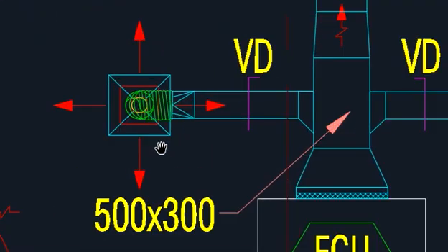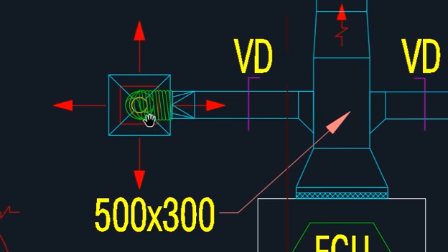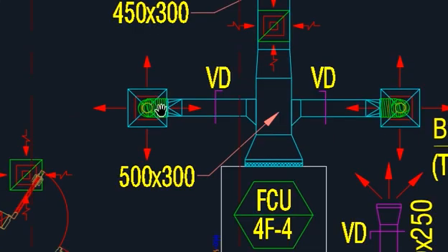Whenever you have to provide diffuser grills or whatever, you have to connect with a flexible duct. The flexible duct, as per standard, must not exceed 1.2 meters. If it is more than 1.2 meters, or 1.5 meters, this is not acceptable. So 1.2 meters is very good and sufficient.